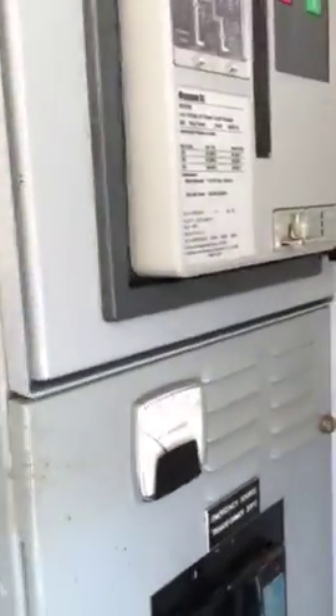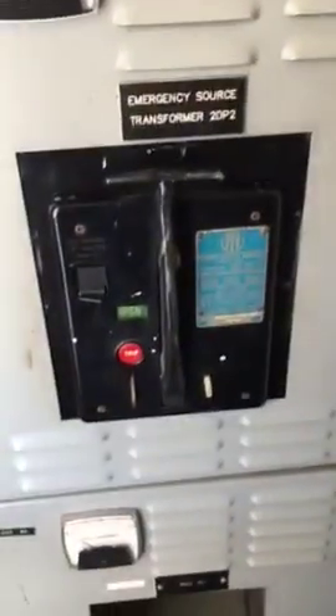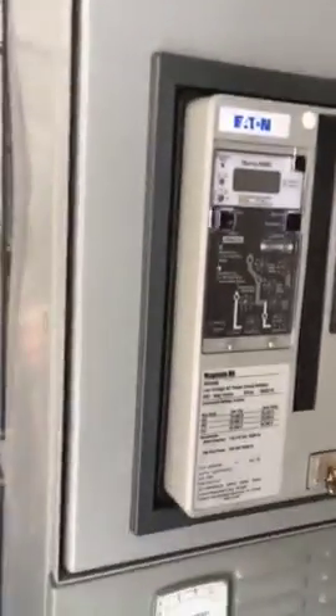One of the other things that we do with these projects is this cell, this original ITE breaker, is rated at 30,000 amps. This brand new Magnum breaker is rated at 65,000 amps. This custom bus work behind here, we actually do the engineering to bring the entire switchgear lineup up to 65,000 amp rating. Just something to note from a selling perspective, it's called a bus bracing study, and it would be a separate line item than just the breaker and the retrofill kit itself. Here's a picture of the front of the gear. You can see the original ITE breaker, and then zoom out a little bit to the Eaton breaker.